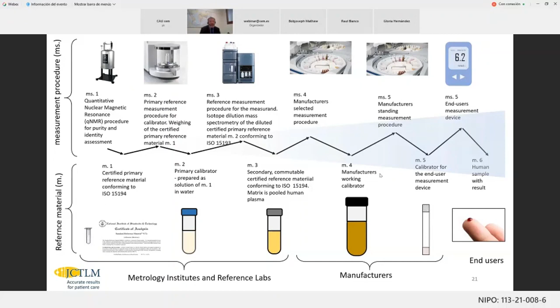We can go from, for example, using NMR, nuclear magnetic resonance, to look at the purity of materials, accurate weighing systems to produce calibration solutions, mass spectrometers to develop reference methods for the measurement of glucose in serum, and then onto the manufacturer's system where they can make fit-for-purpose calibrators, with commutable reference materials. Commutable means showing the same properties as human samples, which can then be used for calibration of the end user measurement instrument.